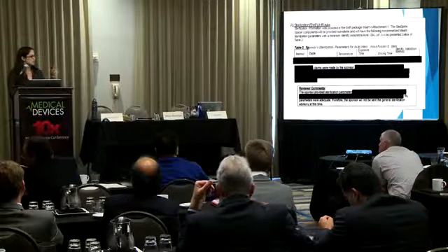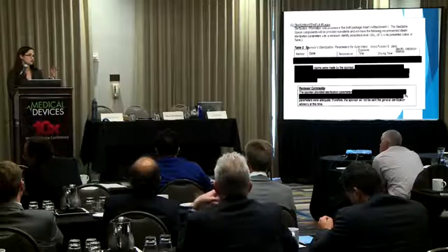In the sterilization section that Rob talked about, I've now started calling it the sterilization cleaning section. Because if there is a cleaning process, you've just seen it so much in the news, like tissue being left on inside the lumen of a screw, or a screwdriver. It's terrifying. So they're becoming more vigilant with a lot of the cleaning validations and just wanting to know that it's been done.